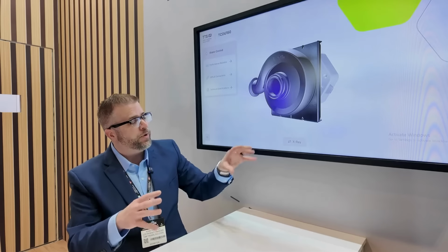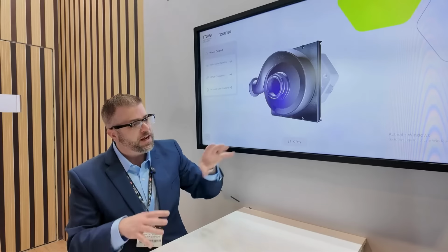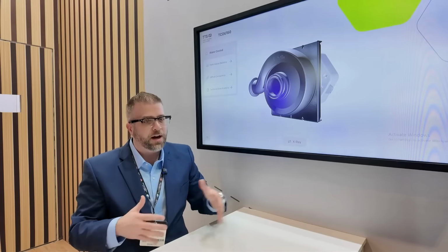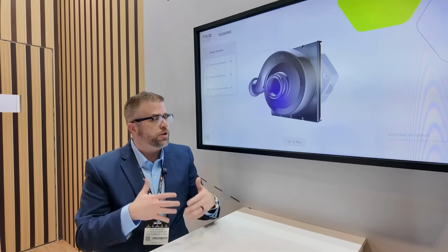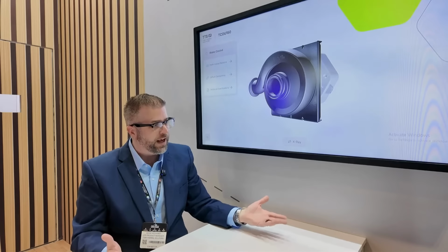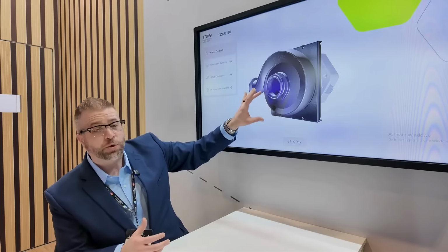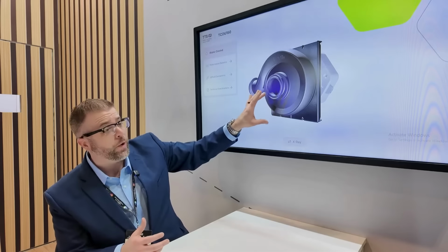Absolutely. The 1 megawatt rack, they're out there. I mean, we're seeing CDUs today that are already hitting 2.3 megawatts for a CDU itself. What we are interested in is how do we not just support the in-rack solutions, but also move into an in-row product, or even look at single and two-phase liquid cooling loop applications. We don't have a digital twin of our RT series, but the RT series is a regenerative turbine pump focused on refrigerant-based applications, again, for single-phase and two-phase liquid cooling loops.